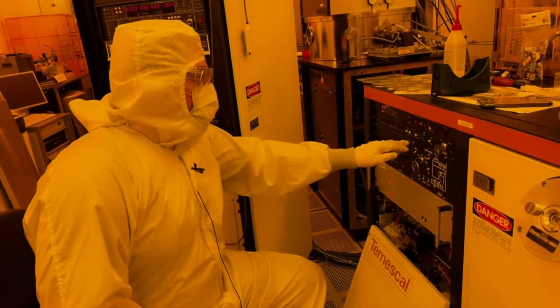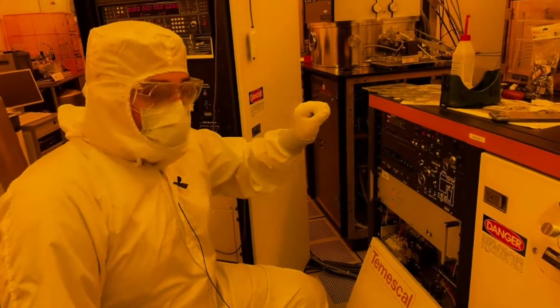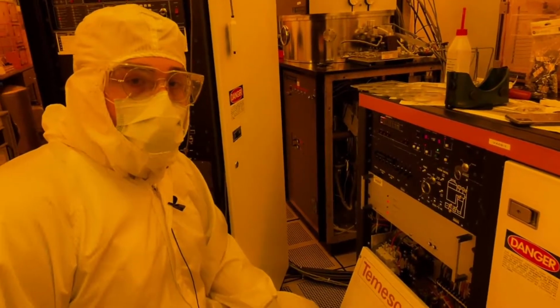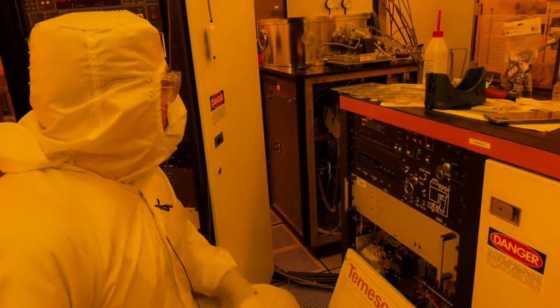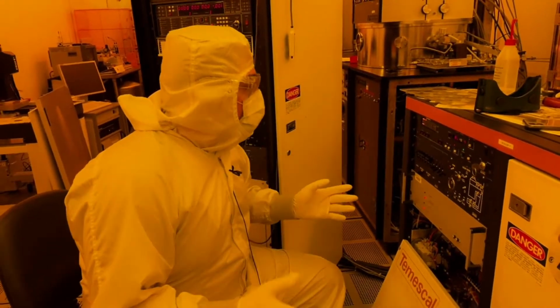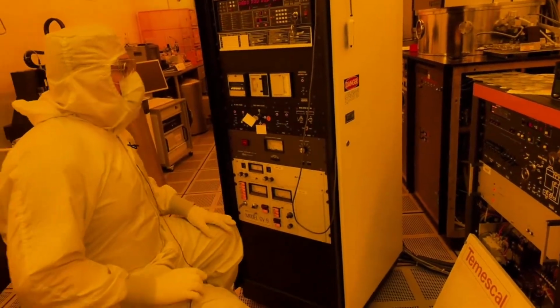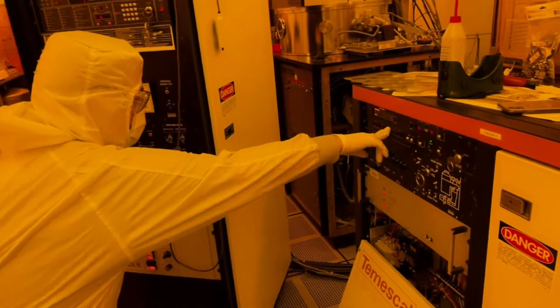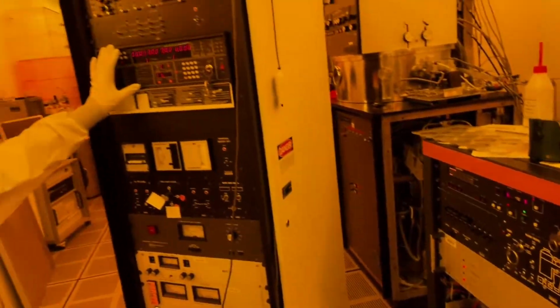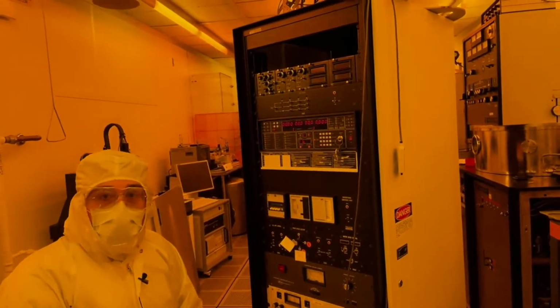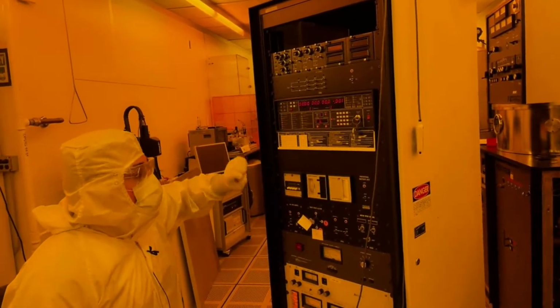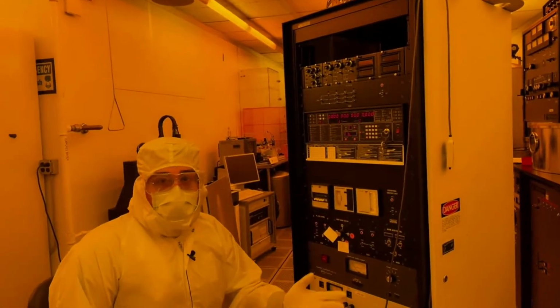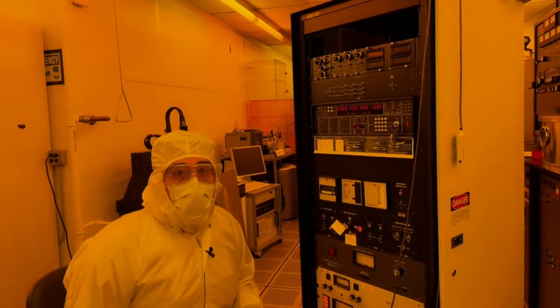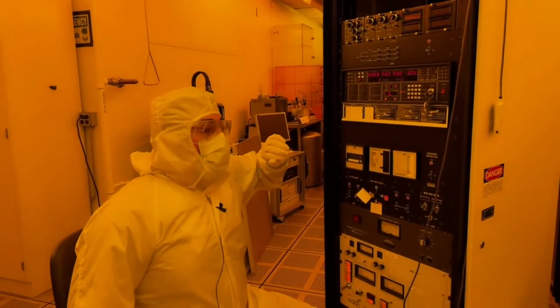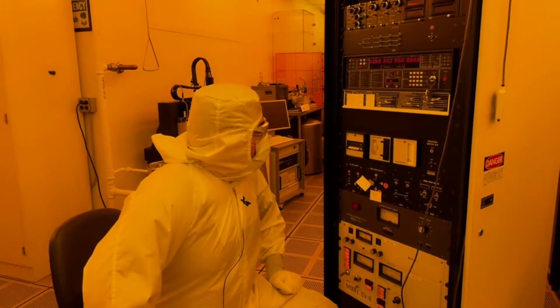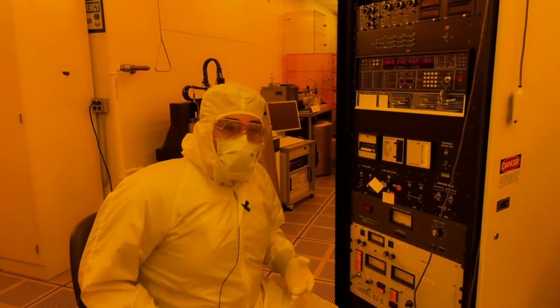Again, I mentioned before, don't press the ion tube button. That will mess it up. You have to discharge the capacitors. Other than that, as far as troubleshooting, when the power goes out, you may have issues where your set points here get messed up or your recipes here get messed up. You just have to be mindful of that. It's possible that this stuff is going to get messed up, and you may have to reset it. So it's always good to have a backup log of what your recipes are and what you should set them to. So that's pretty much all of the issues that we've encountered with this system.